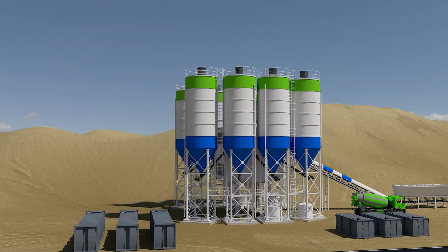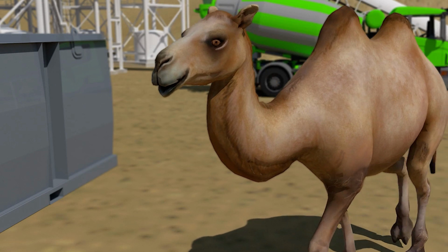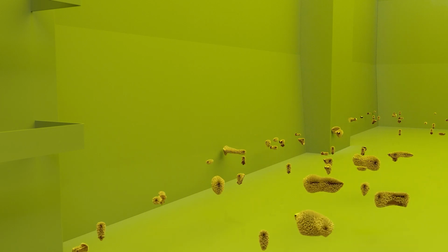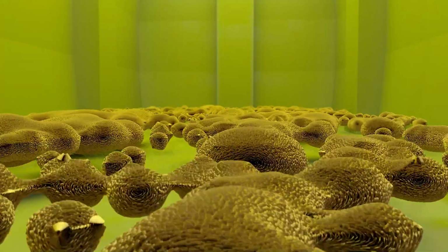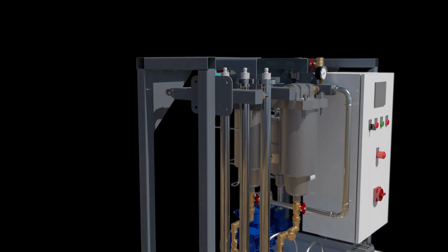In warm regions of the world, microbial infestation of fuel stores repeatedly leads to major damage to internal combustion engines in machines, generators, and aircraft. To blame is the problem of diesel plague. The interaction of microbiology, high outside temperatures, and condensation in the fuel leads to the rapid growth of microbes in the bottom area of the fuel tank, which can result in all the fuel in the tank being unusable within a very short time. But there is a remedy.